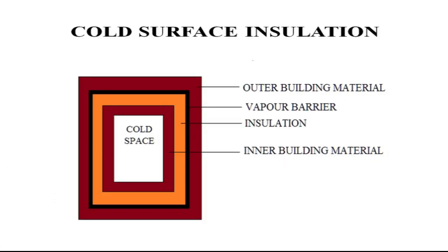In a cold store, the construction layers from inside out are: inner building material, then insulation, then vapor barrier, then outer building material. The red color represents masonry structure (brick work, cement, RCC); the orange colored material is insulation; and the black colored material is the vapor barrier. Both kinds of materials have already been explained.